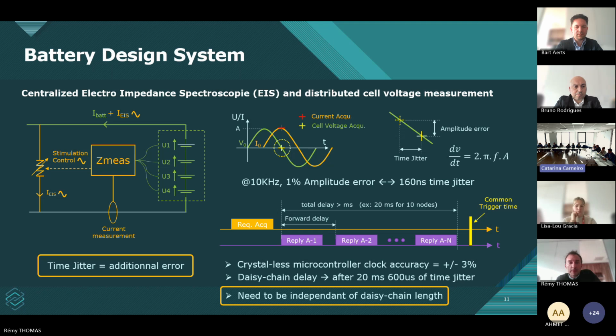Temporal accuracy between current and voltage measurements is crucial for two reasons. First, impedance depends on both the amplitude and phase of the signal response. The relation between phase accuracy and temporal accuracy is straightforward. But temporal accuracy can also impact amplitude accuracy. It can be estimated that for a sinusoidal excitation frequency of around 10 kHz, an amplitude error of 1% can be produced by a time jitter of only 160 nanoseconds.